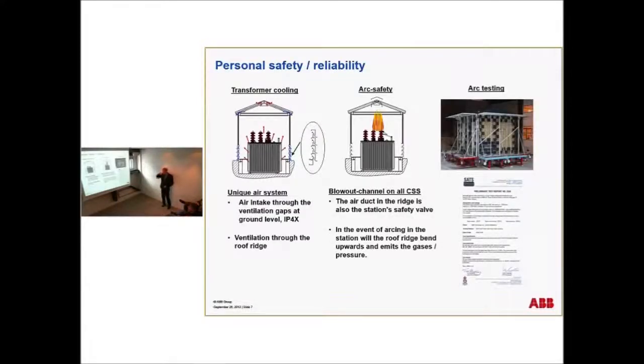More about personal safety. The roofing solution, we have a unique air system. It's through the ventilation gaps at ground level. The ventilation will go through here and go up here. And of course, we have this filter we can put in here, and here. And as you see here, it's also arc safety. If an internal arc occurs, the valves on the arc channel or the ridge will blow up, and all the pressure will go up on the roof.